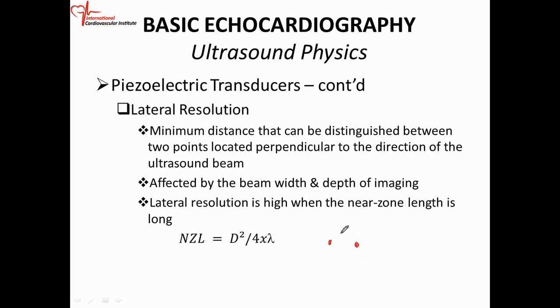The ultrasound beam is going to be perpendicular. It's going to come down. It's going to be perpendicular to the points. So it is still the distance, spatial resolution, which encompasses both lateral and axial resolution. These are spatial resolution. So it is the minimum distance that can be distinguished between 2 points located perpendicular to the direction of the ultrasound beam. So the ultrasound beam is coming straight down, which is perpendicular. And you still can see these 2 points, even though they might be very close to each other. You still see them as two distinct points. And so when you get a television, you want to make sure that the television has a high resolution so that you can see two distinct areas close to each other. Okay? So the ultrasound is the same thing. But this is lateral resolution.